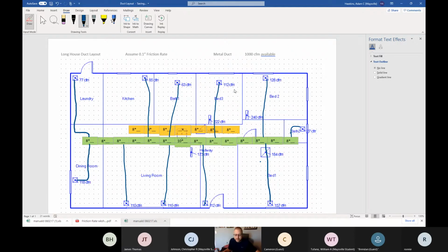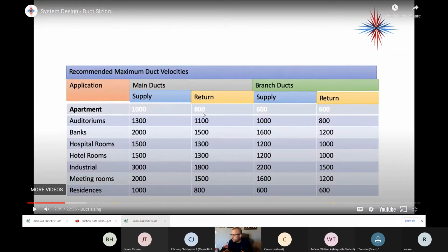So in your spreadsheets, it should give you room by room loads when you go to that breakdown, and then it should also convert those room by room loads to CFMs, which is the amount of air that you're actually going to need for that room. He does in this video kind of go into calculating, toward the end here, if you knew BTUs, but it didn't give you the static or the CFMs per room.